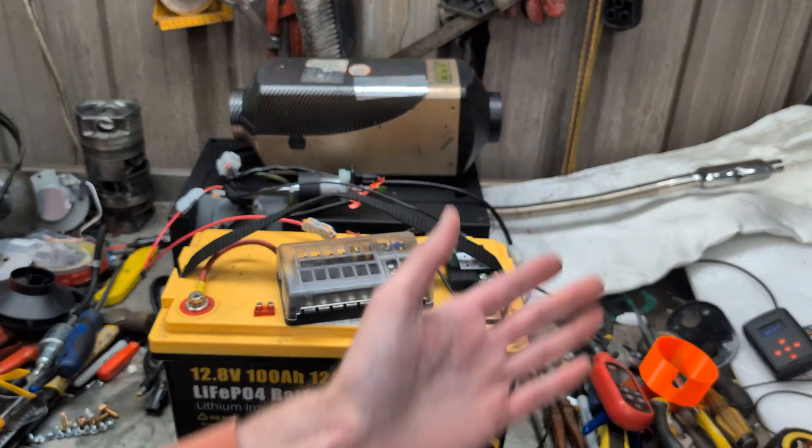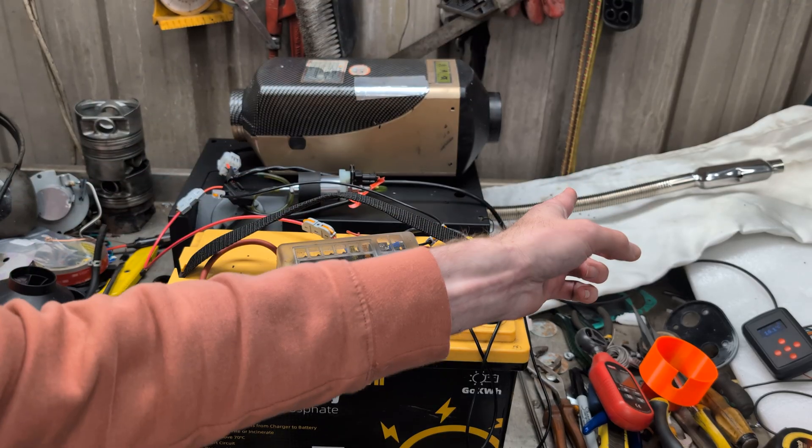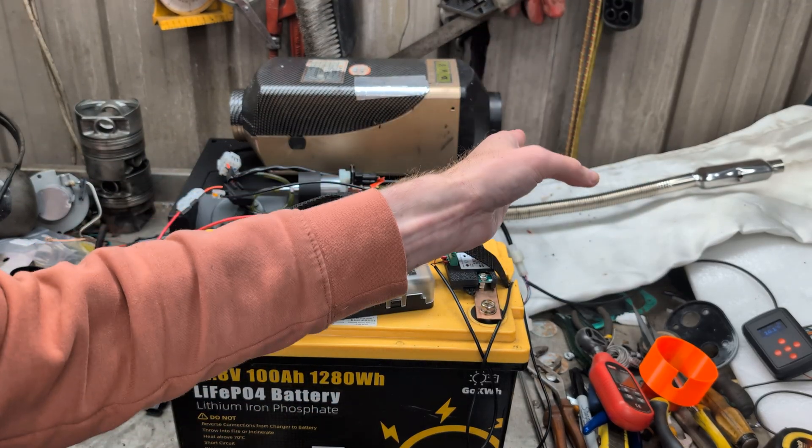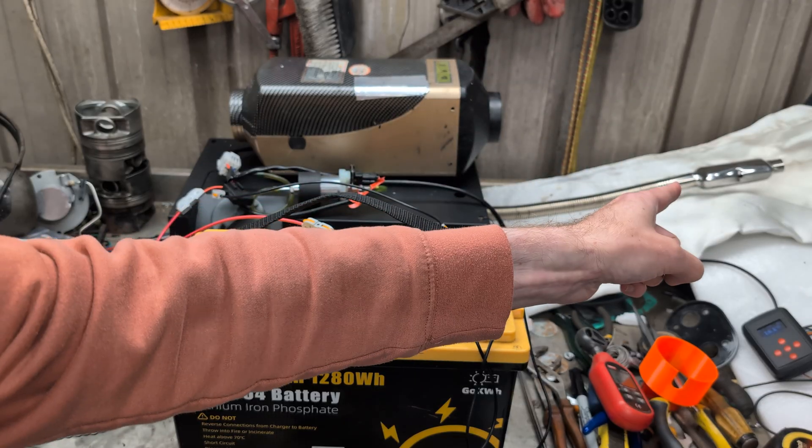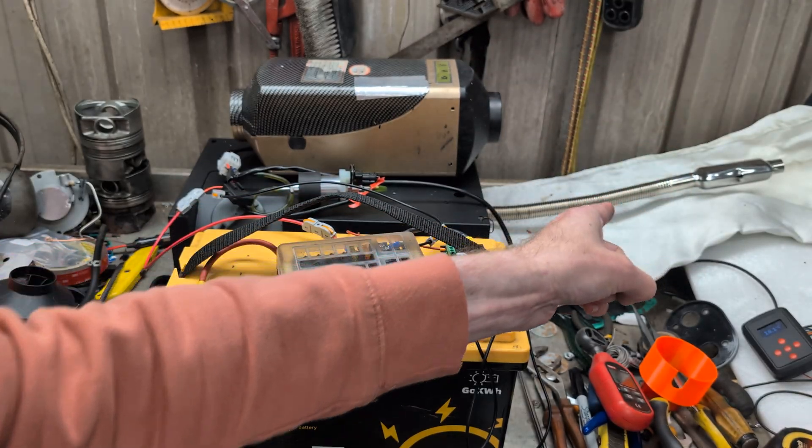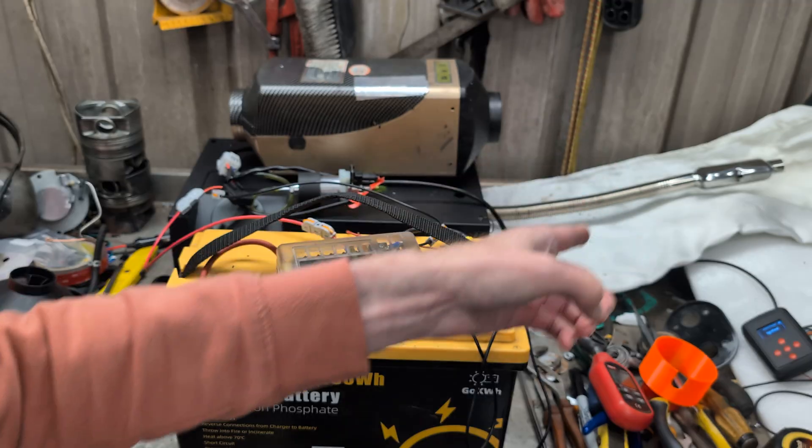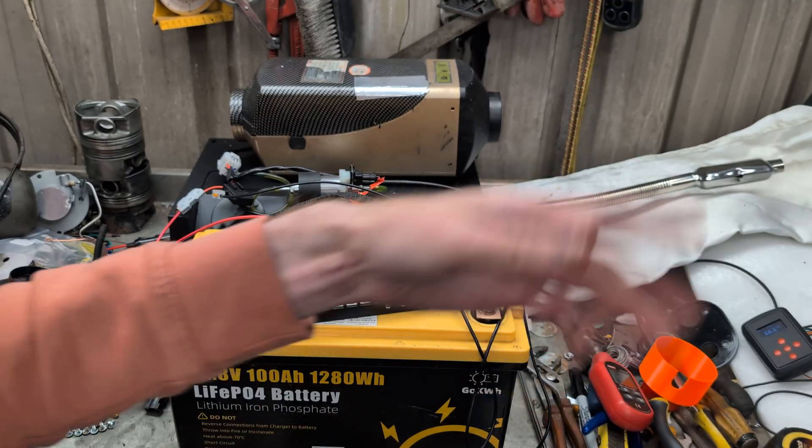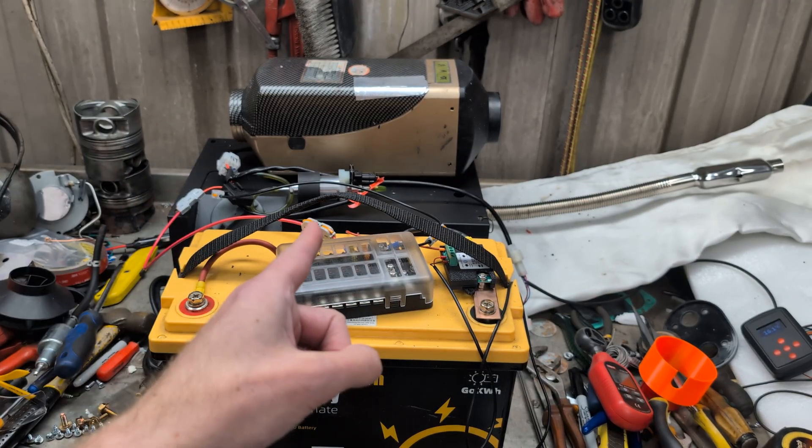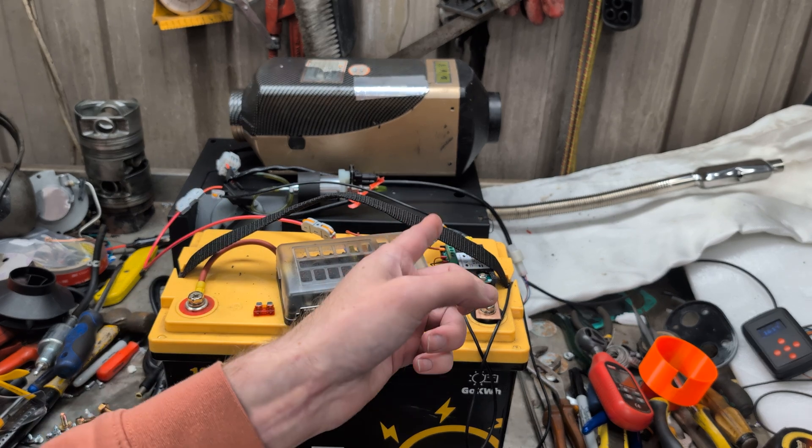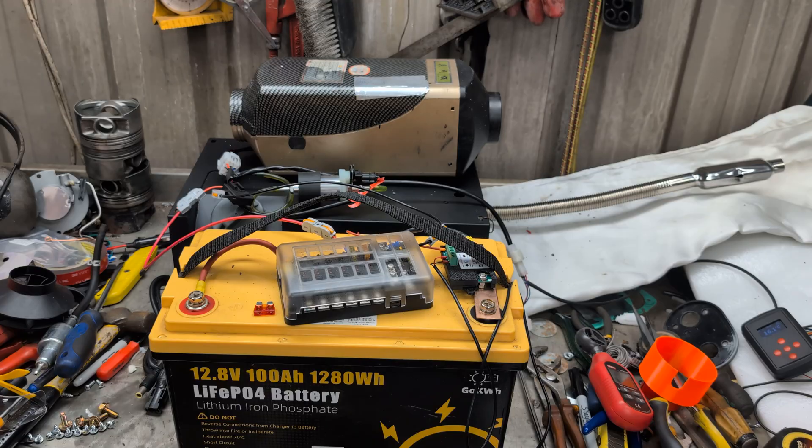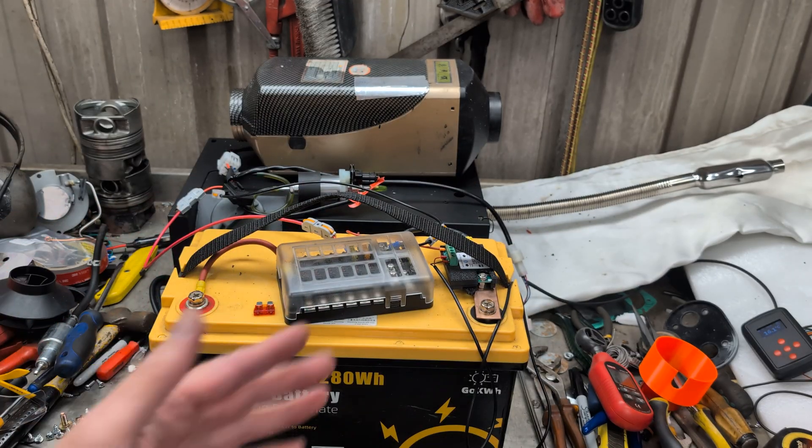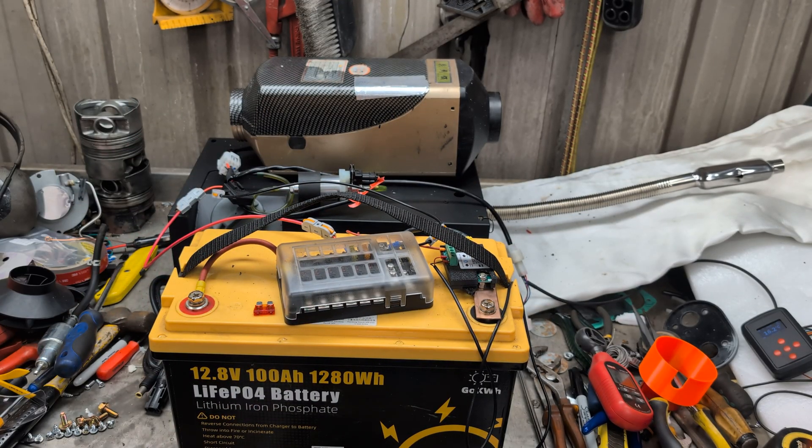Basically the test is going to be air intake temperature, air output temperature, wind speed output, and I'll put the gas analyzer in the exhaust silencer. We'll get an exhaust gas temperature reading and the carbon monoxide reading. So that heater is lit, which means I'm now going to leave it for half an hour, get fully heat soaked and fully up to temperature, and then I'll start taking readings. I'll bring you back if anything exciting happens or once I've taken all the readings.